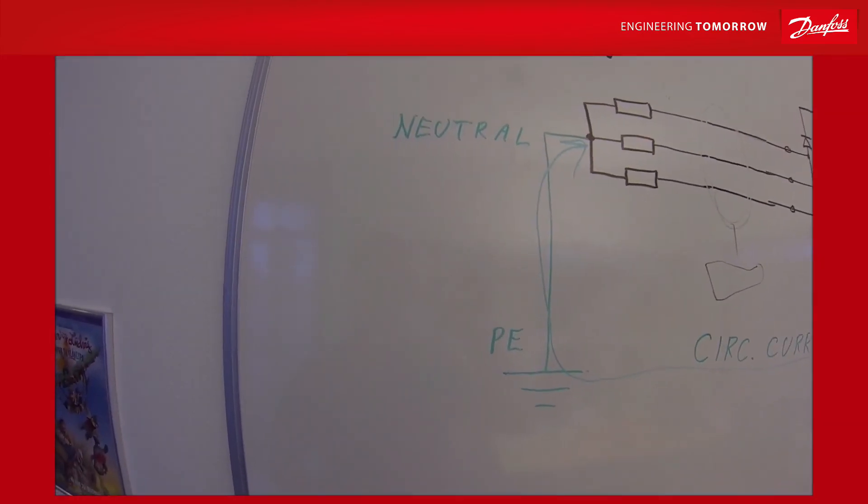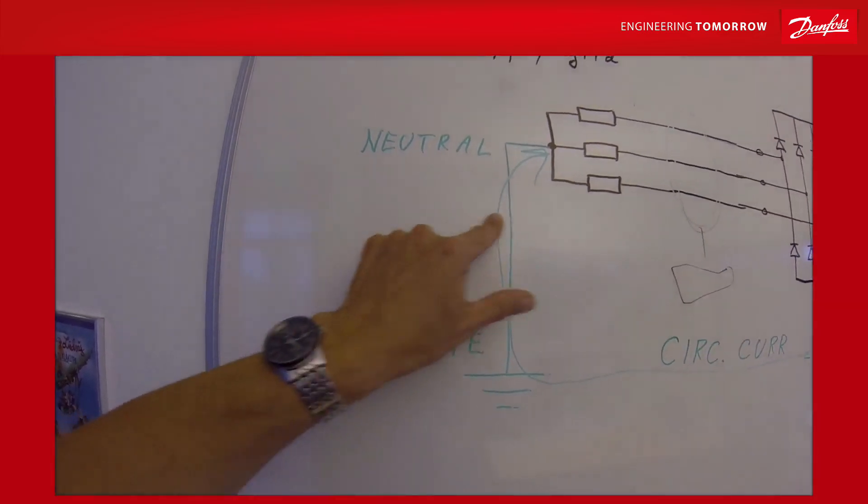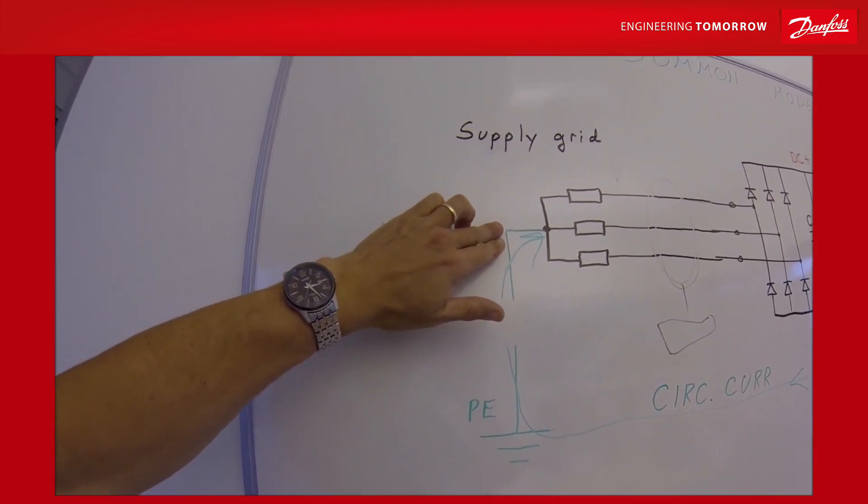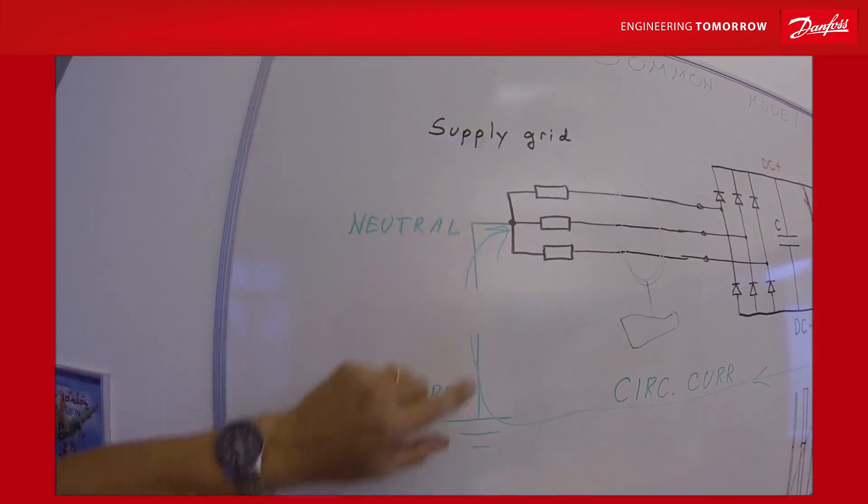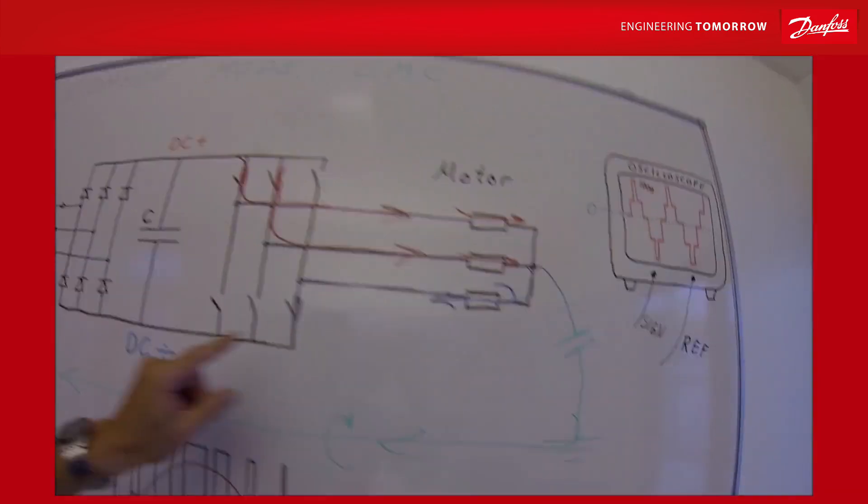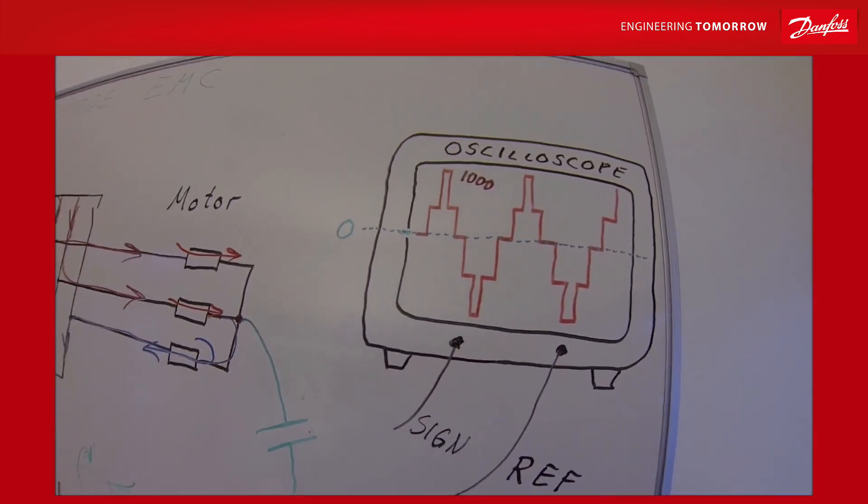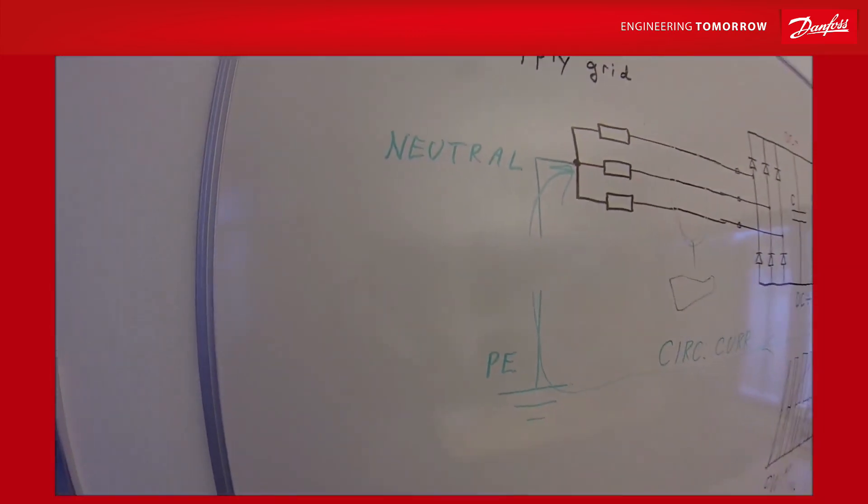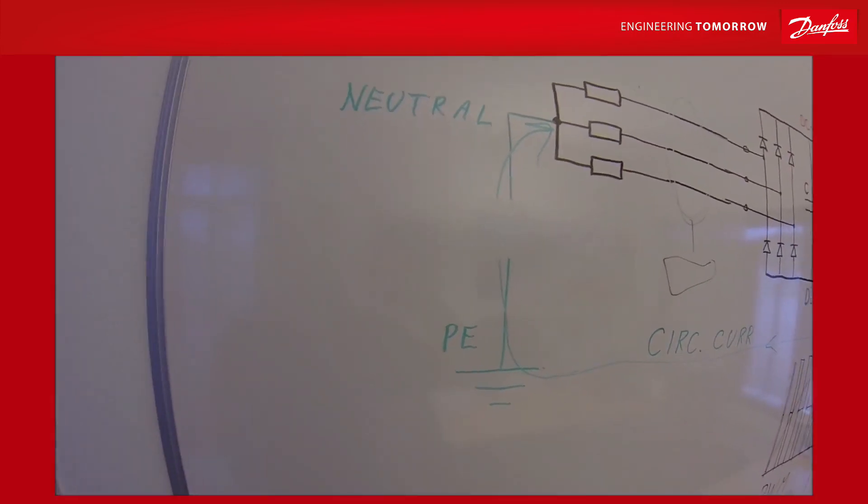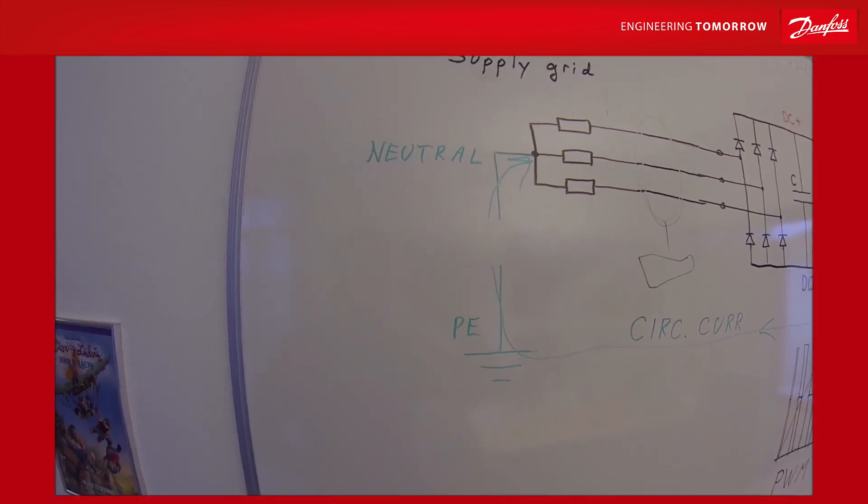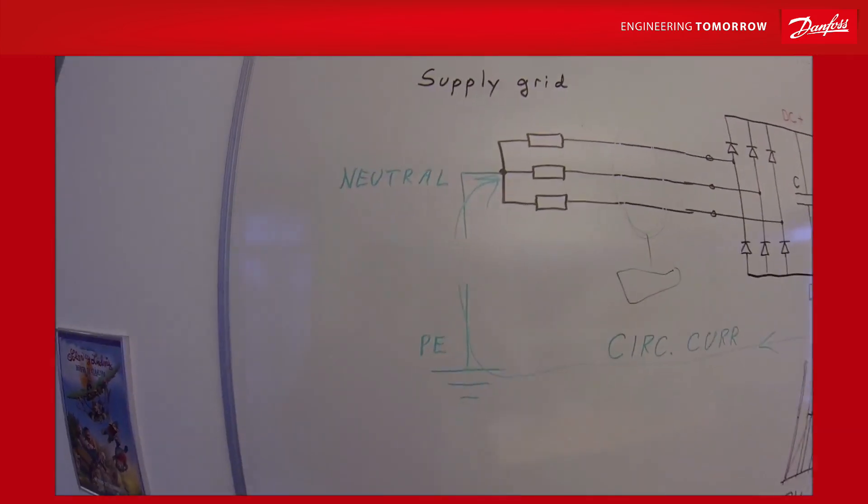Also, some earth fault and insulation metering systems are placed here in this point. It can measure any voltage difference between the neutral point in the generators and transformers and the protective earth. It will also see this common mode, of course. If there is a connection between here and the protective earth, it will see this and it will trip. The answer again is to have an insulation meter which is built for frequency converters. There are many vendors that have this equipment. Bender is one of the best. This one will differentiate between high frequency voltage and the 50 Hz, the real problem.